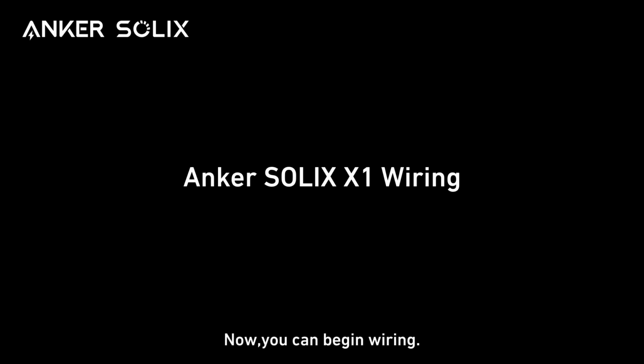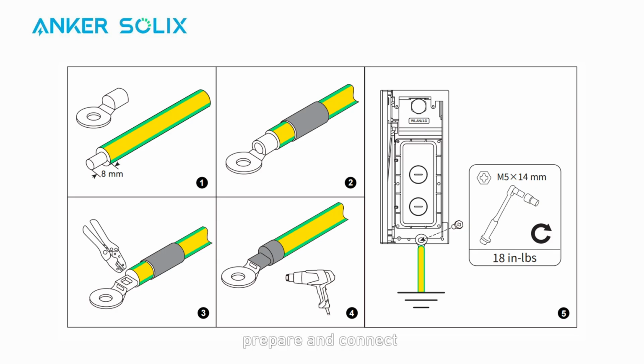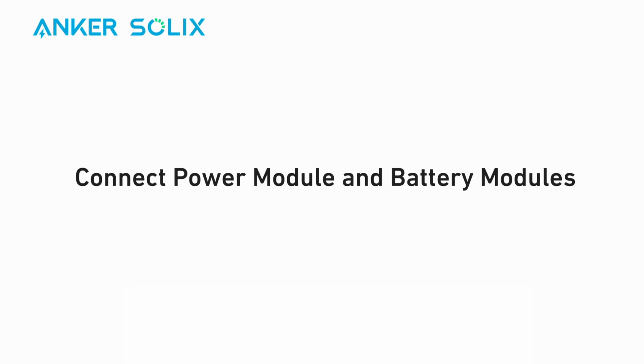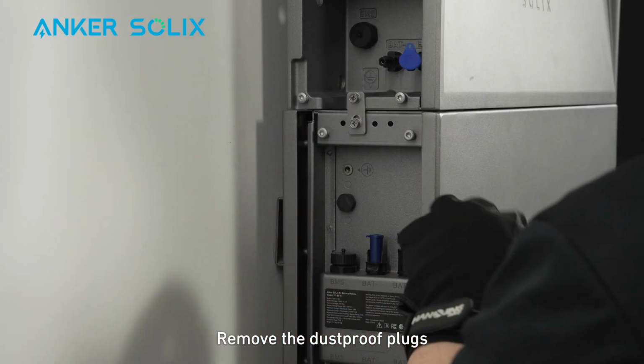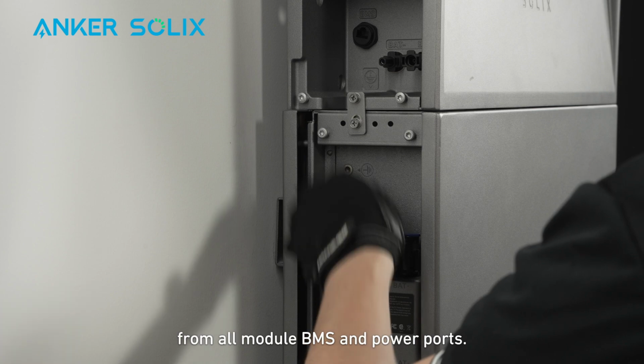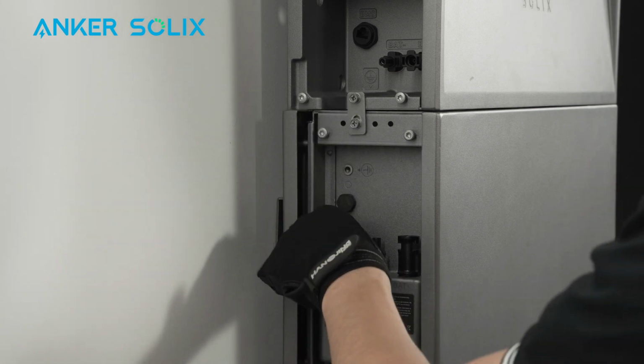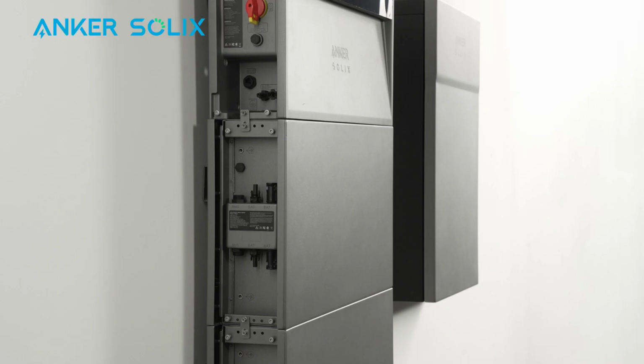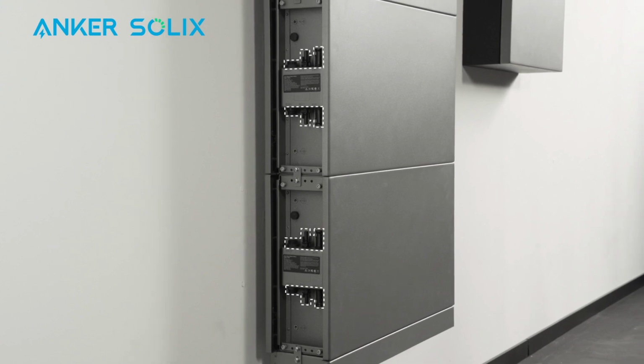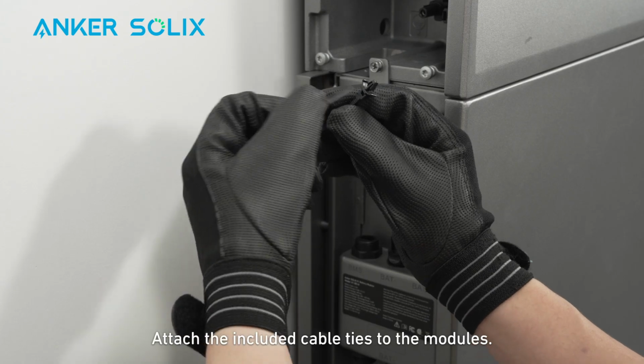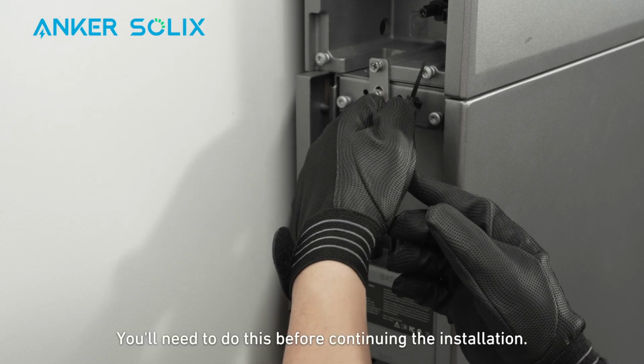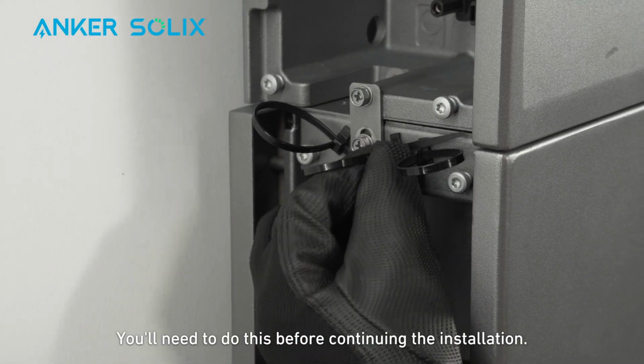Now, you can begin wiring. First and foremost, prepare and connect a GND cable from the power module to the external ground point. Remove the dust-proof plugs from all module BMS and power ports. Attach the included cable ties to the modules. You'll need to do this before continuing the installation.